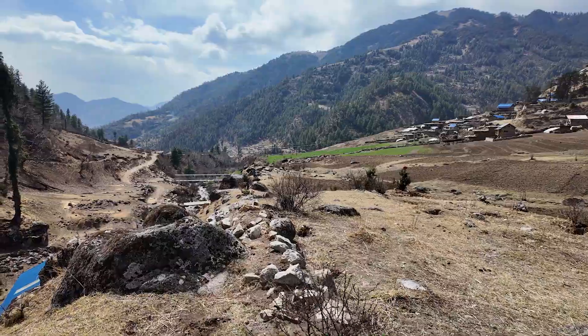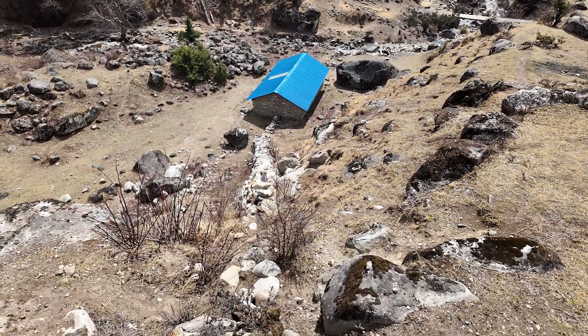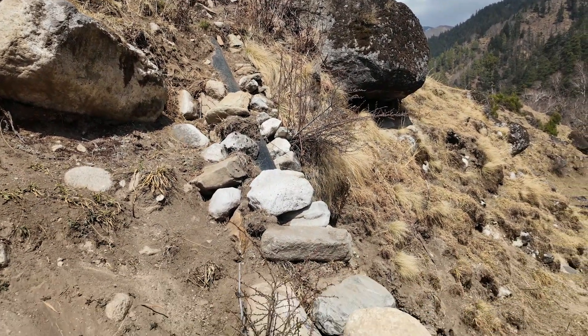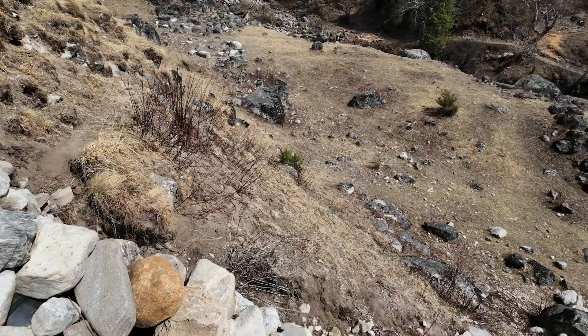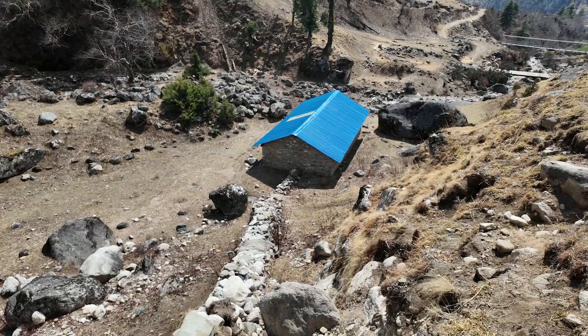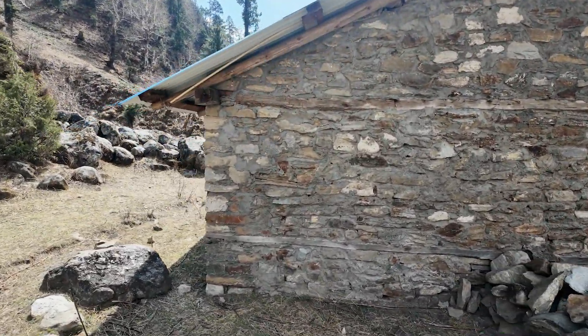Here we come to almost the end, reaching the ridge before the steep fall of the penstock down to the turbine house. This is the last part of the 495-meter penstock from the sedimentation tank down to the turbine house, where of course the thickest 200mm high-density polyethylene pipe is used, rated at 6 kg per square centimeter pressure. And there is the turbine house, which we are going to see now — here are the last few meters of the penstock leading into it.